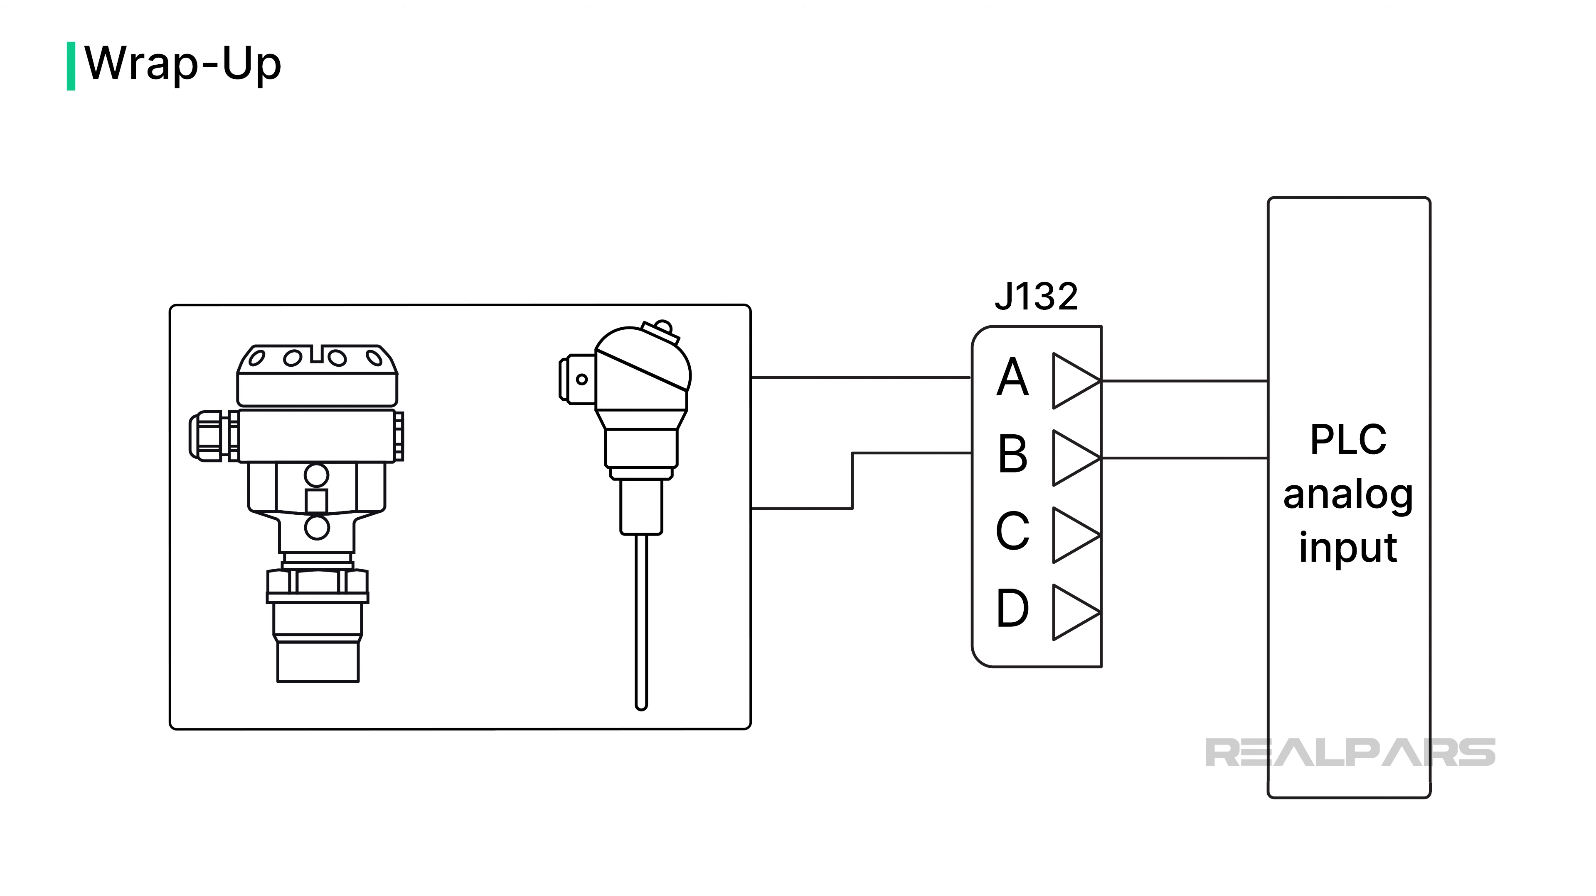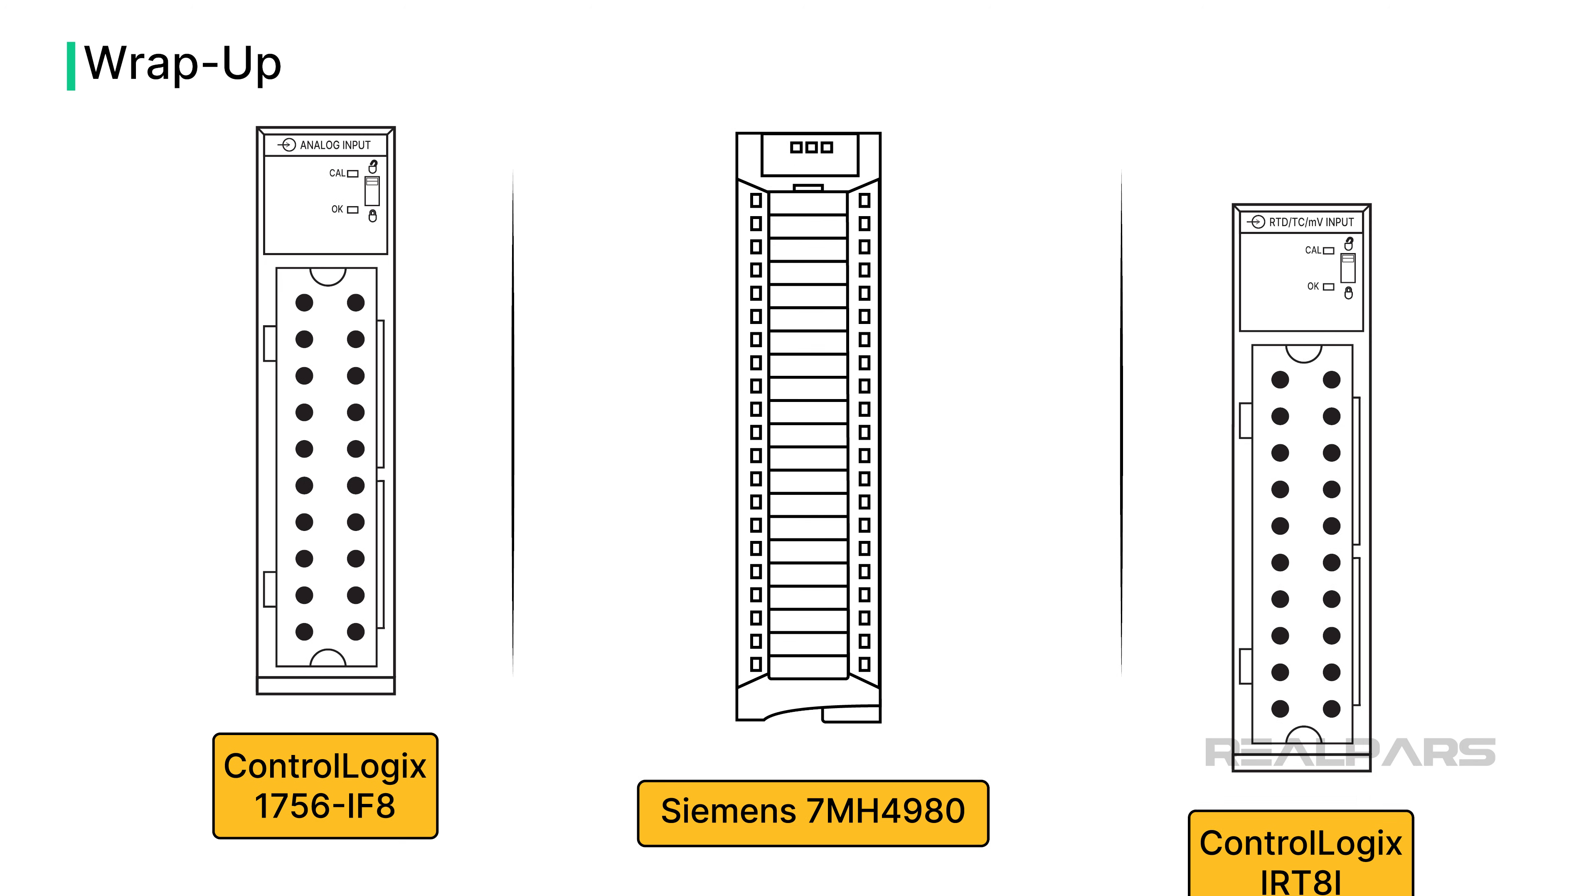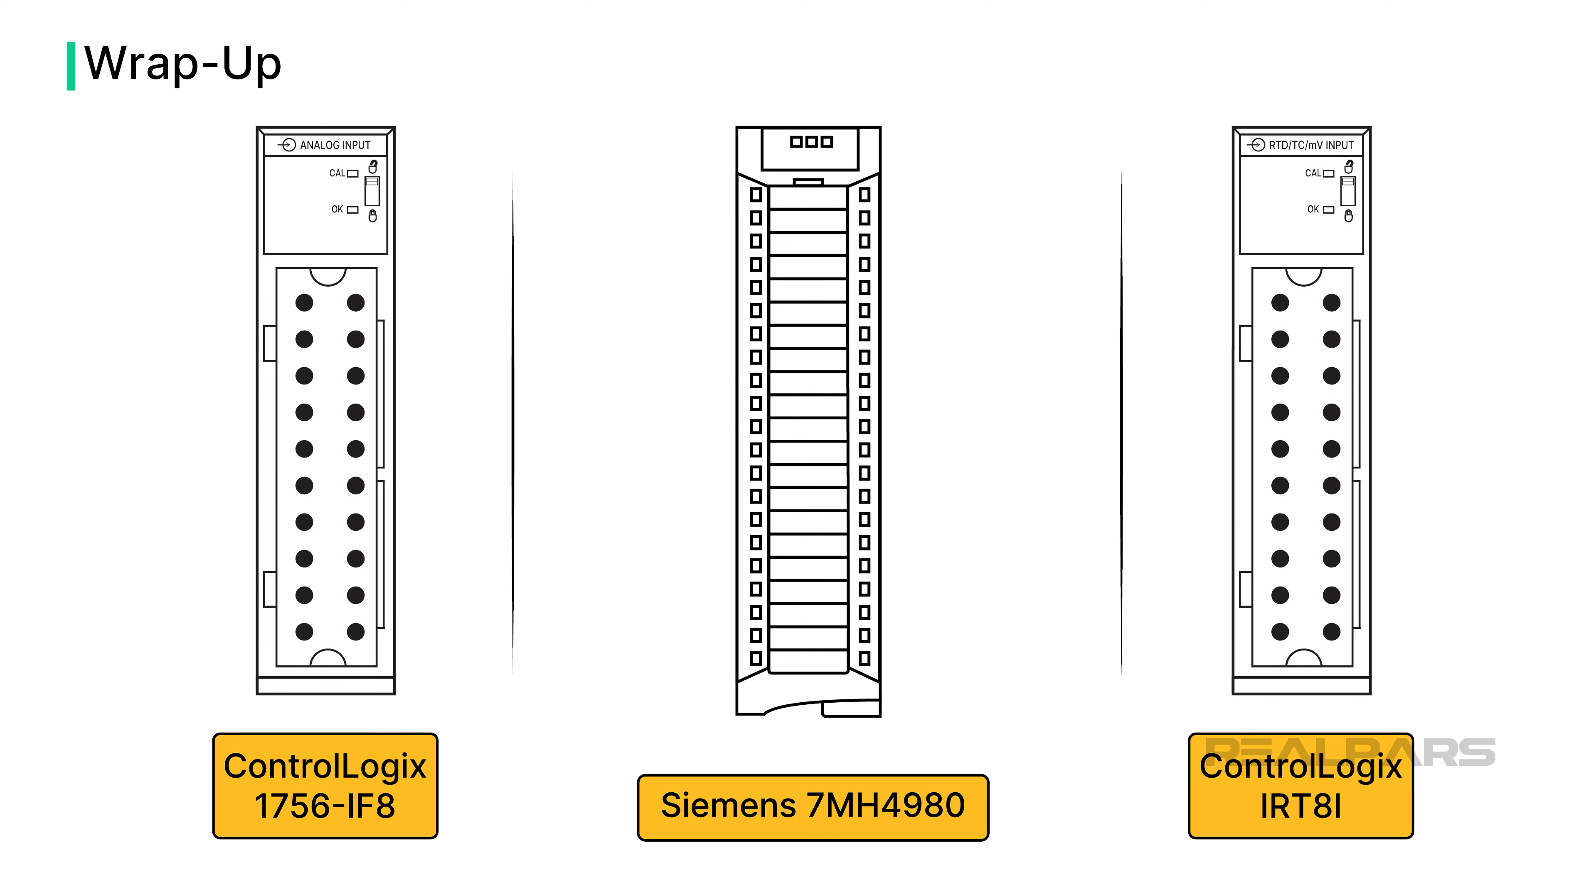Typical analog voltage signals include 1 to 5 volts, 0 to 10 volts, and negative 10 to positive 10 volts. The most commonly used analog signal is a 4 to 20 milliamp current. PLC module vendors offer analog input modules that can be used in multiple process variable loops.